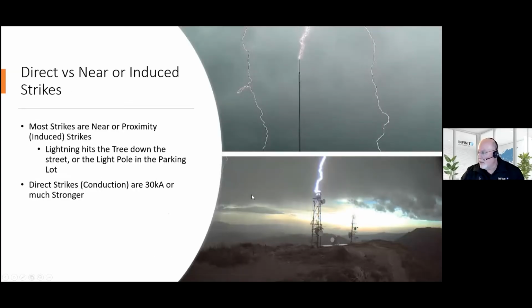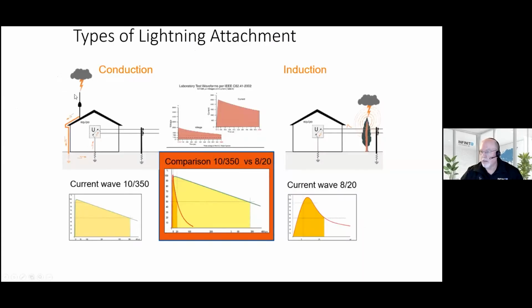And now about lightning. When lightning hits things, it's either a direct strike or a near strike. Now, most strikes are near strikes. It hits the tree down the block, the light pole in the parking lot. In this example, it's a near strike event for that tower. This is obviously a direct strike. Lightning, being a natural electromagnetic pulse, will induce surge currents in all conductive cables and things within its sphere. So this tower, even though it wasn't directly hit, is susceptible to lightning-induced surge currents. Another way to put it is conduction, direct strike, or induction, near strikes or proximity strikes.